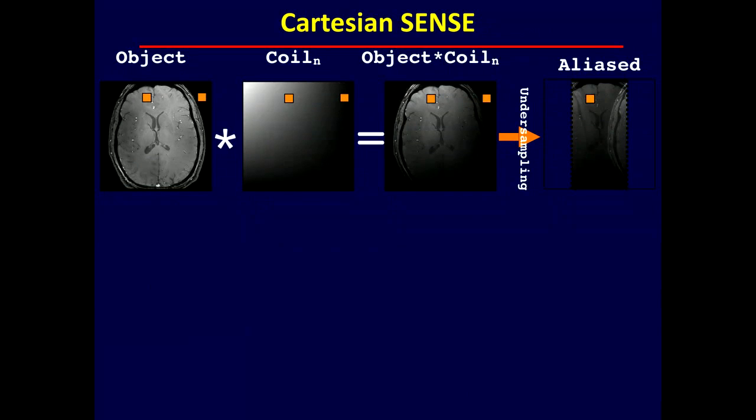Right. And you had a question about why there is no aliasing in the readout direction. Readout direction and phase direction. Does that make sense? There's no aliasing in the readout direction. Do you know why? Yeah, there's an anti-aliasing filter there. So whatever happens outside the field of view is already filtered out before you digitize it. That's why there's no aliasing in that direction.